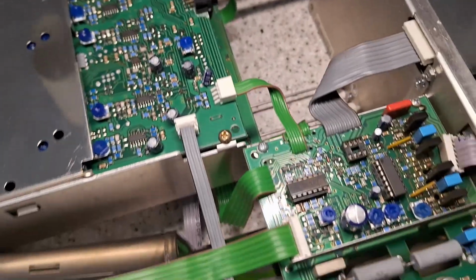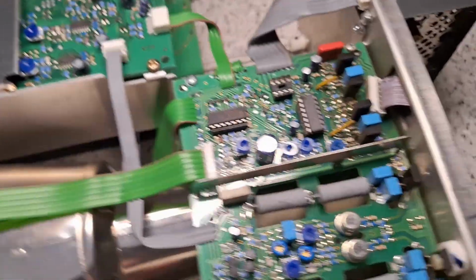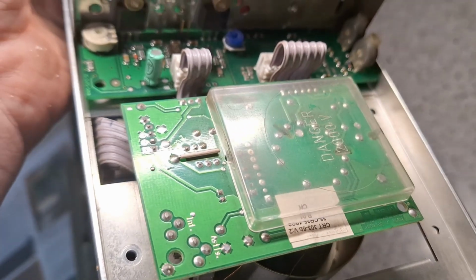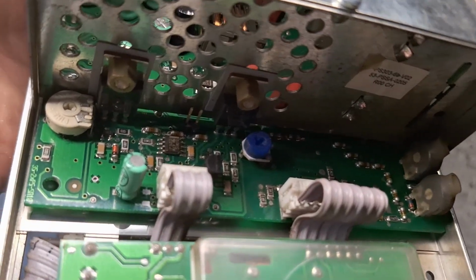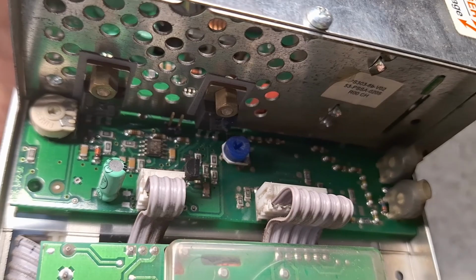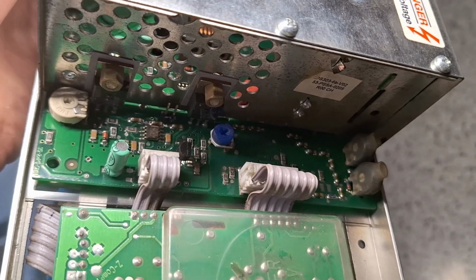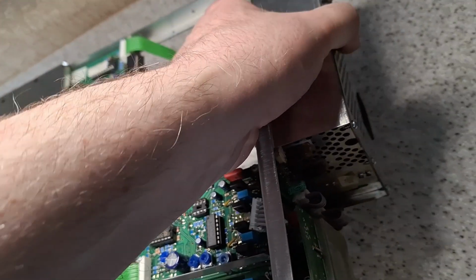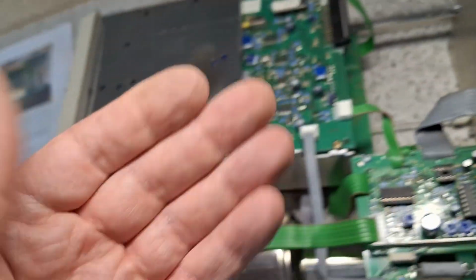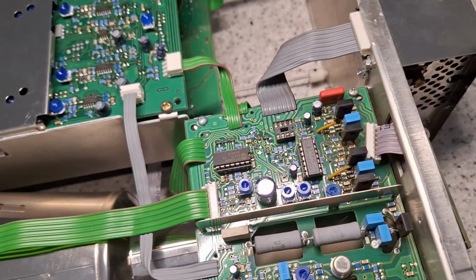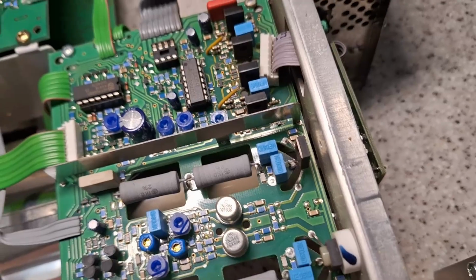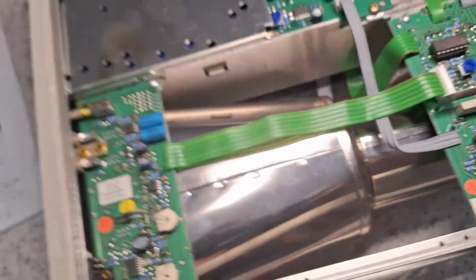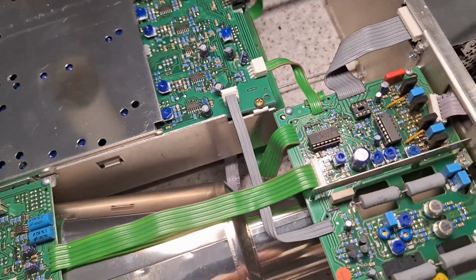The only thing I can't check is the high voltage to the CRT, the 2000 volts, because I haven't got a high voltage probe. So that is on the back there. See if you can see that. Now the power supply is different on this one to what's listed in the service manual, and the schematic is different again. But they're all HM303-6s, so obviously the voltages are the same. So I suspect with this scope, there's no high voltage.